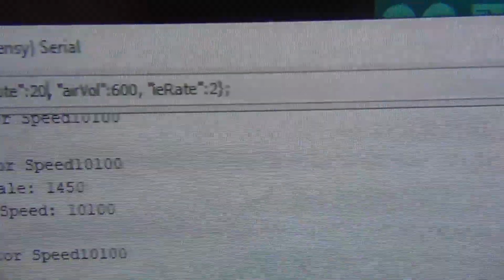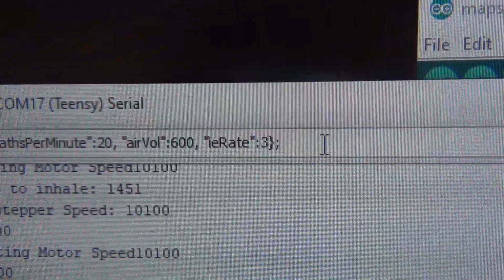Okay, so this is the API that I actually have at the moment. You control these two parameters. Before, I had it some weird way for testing stuff in percentage, and people complained that doctors don't use percentages, and they were right. So I made it look like what the doctor would use. So if you want 20 breaths per minute and you want the inhale-exhale ratio. And I also explained what that means because I saw others working on controllers and they got it wrong.